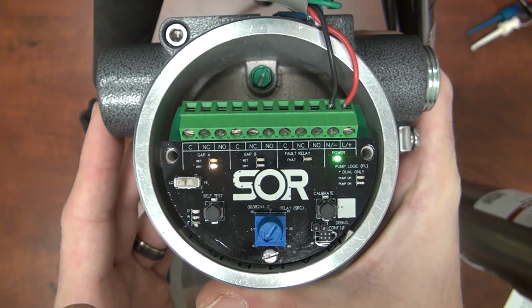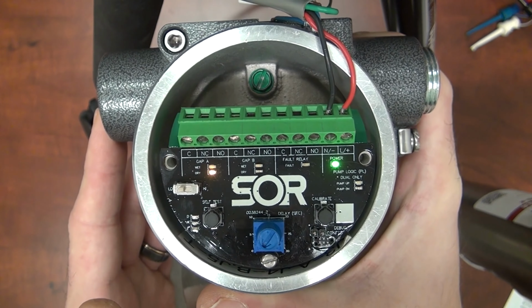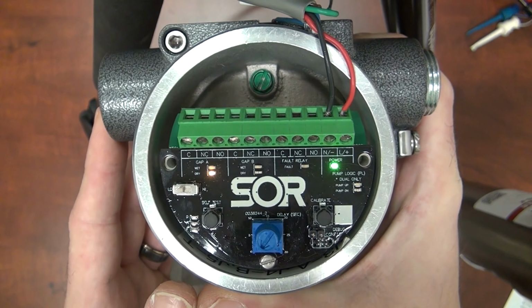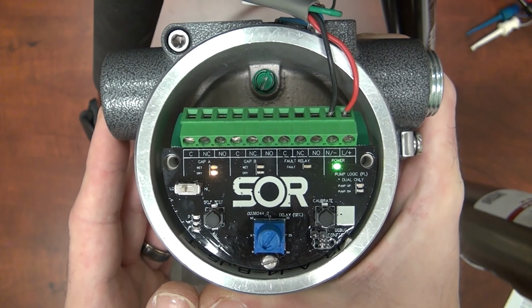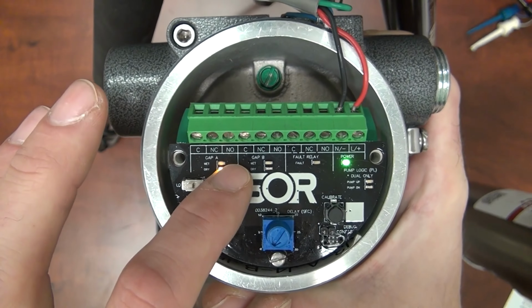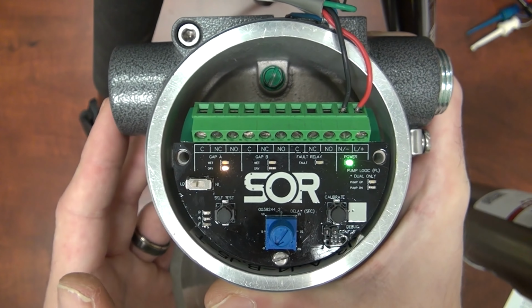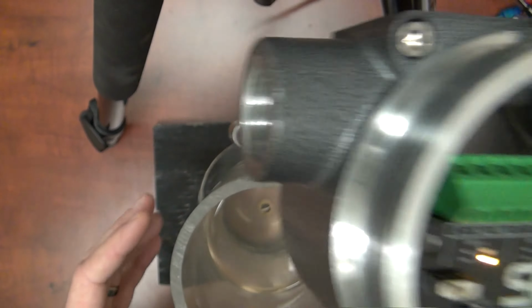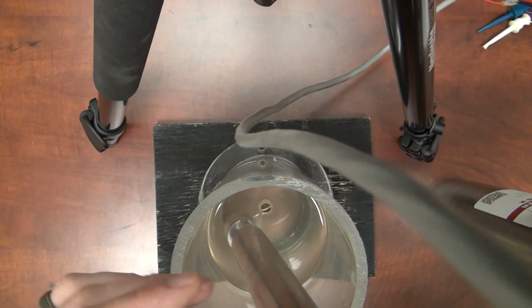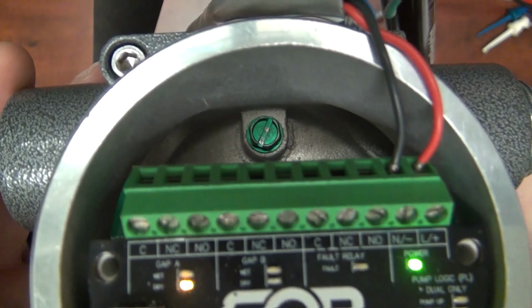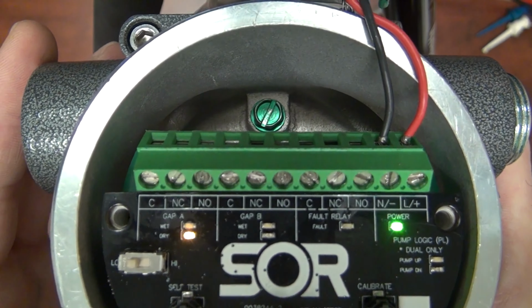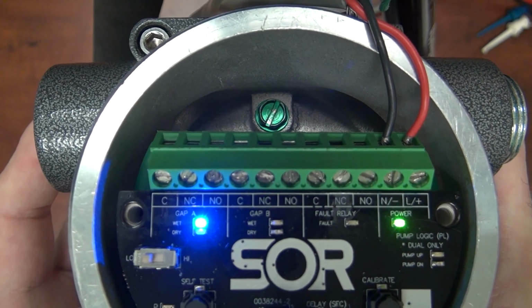Normal operation. When the device operates, it detects if there is liquid present in the gap. This change can be seen with the LEDs in either the gap A and or the gap B. Right now it is empty, but we're going to insert it into this water column. We can see here, as it's inserted and liquid fills the gap, it changes from dry to wet.